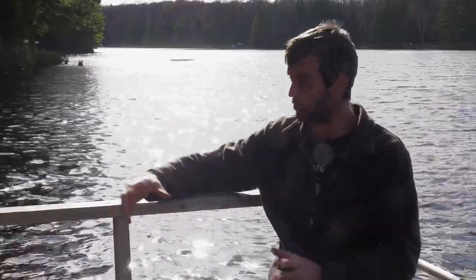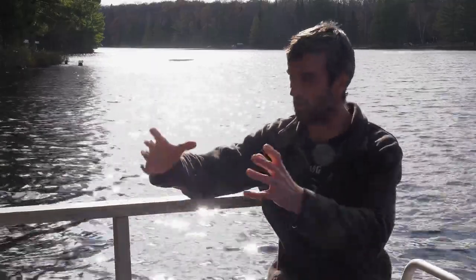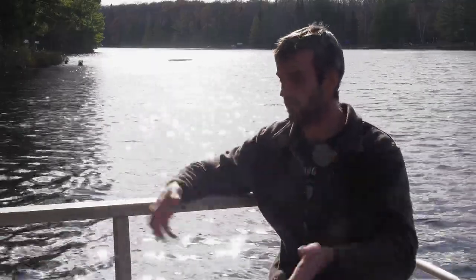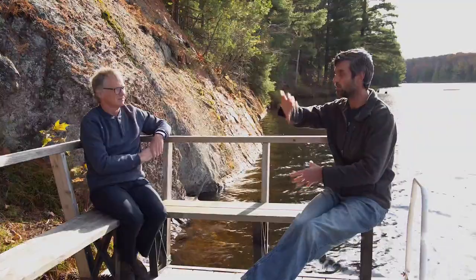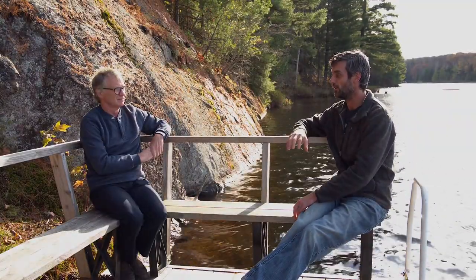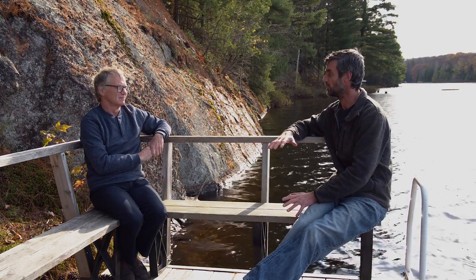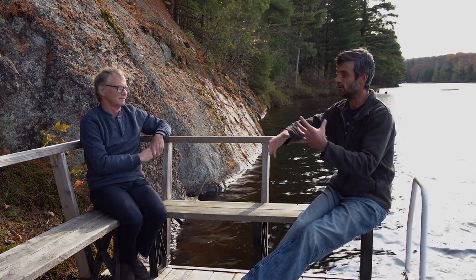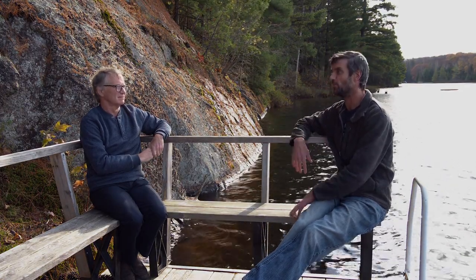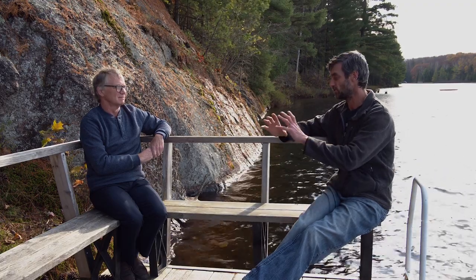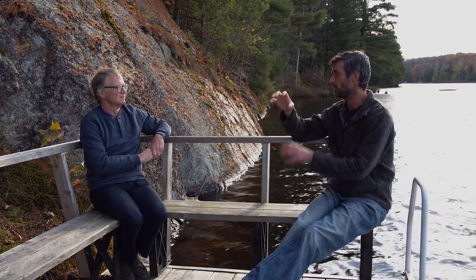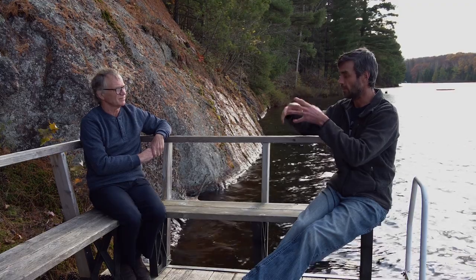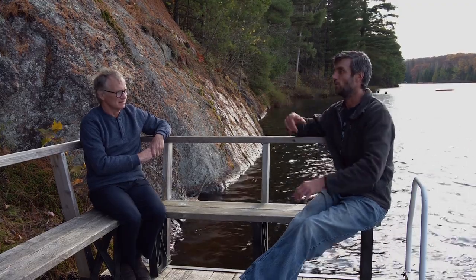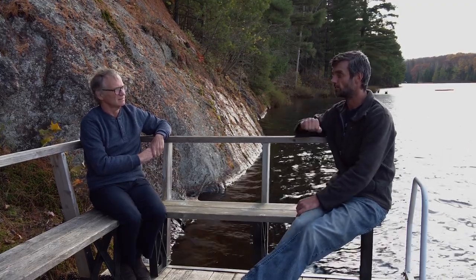That's a whole pump contraption your service guy has to hook up to flush it out. It's fairly time consuming, and then you repurge the air out. And letting air into a hydronic system is the worst thing you could do. So servicing them actually can let a little more oxygen in, which isn't helpful, but it's one of those things. The heat exchanger on boilers, a lot of carbonic acid will build up in the heat exchangers, and in some of the designs it'll actually plug the heat exchanger openings, where the baffles are, where the flame goes through and the water is.